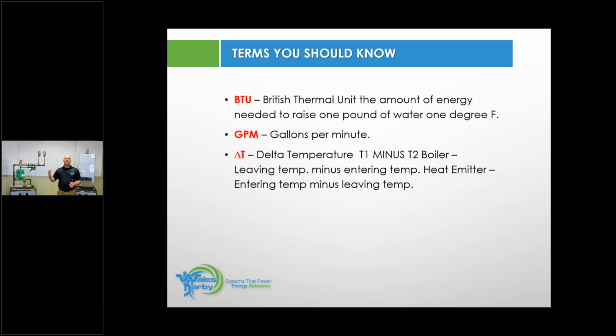GPM, gallons per minute. You're going to hear that constantly. That's going to be in a formula here in a little while. Get familiar with that. The little triangle right there with the T, that's delta T. That's going to be the temperature difference. And Chris, I'm going to have you bouncing all over the place with the camera here.